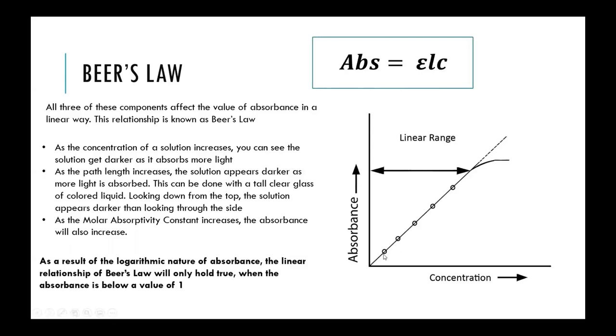However, this linear relationship only holds up to an absorbance of one. Remember, absorbance and transmittance are logarithmically related. That means that after an absorbance of one, it starts to taper off in a logarithmic way and is no longer linear. So when relating absorbance and concentration, you need to make sure that any absorbance value is below a value of one.